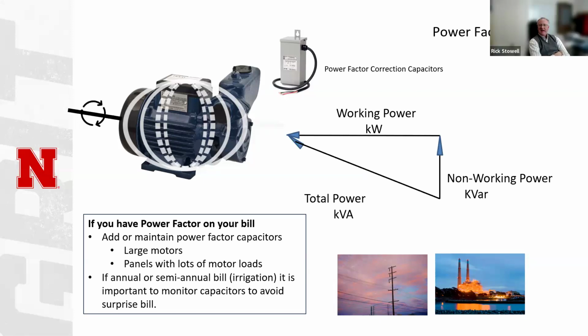So I'll mention a couple of triggers. One trigger I've seen is somebody buys property, they want the land, and they get the old buildings with the land. The old buildings had some motors in them, and they never used the motors, but the utility knows those motors are there. So there's a rate schedule that charges them based on the total kW or horsepower capacity of the site. Even though they never run those motors, they're still being charged for them. They might say to the utility, well, I never turn them on. And the utility says, well, you could. So the solution is to disconnect those, have them taken off the public utility line.